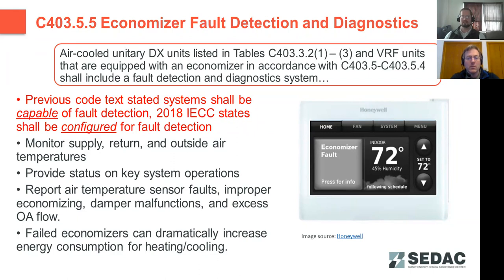The 2018 code did upgrade that language and says that these systems must be configured to do this now. Those systems have to be able to monitor supply, return, and outside air temperatures, different system operations, whether cooling is active or not, whether the economizer is active or not, and report what percent the damper positions are at. So various details, and it should be able to detect any control issues and report back to the operator when there is a fault or some kind of error.